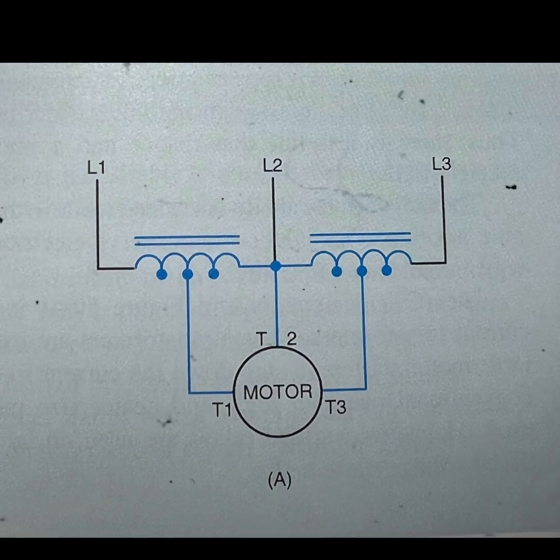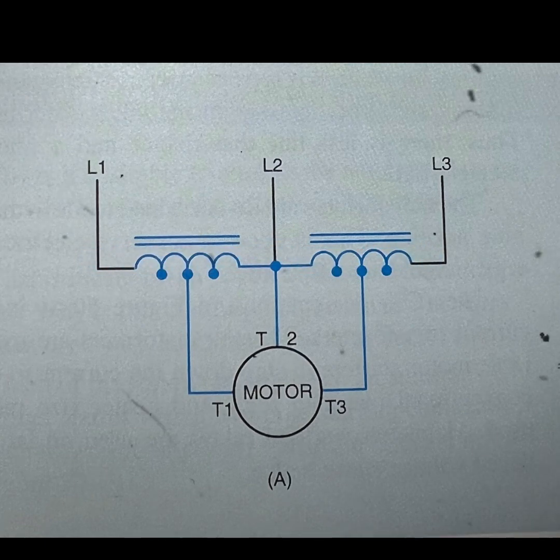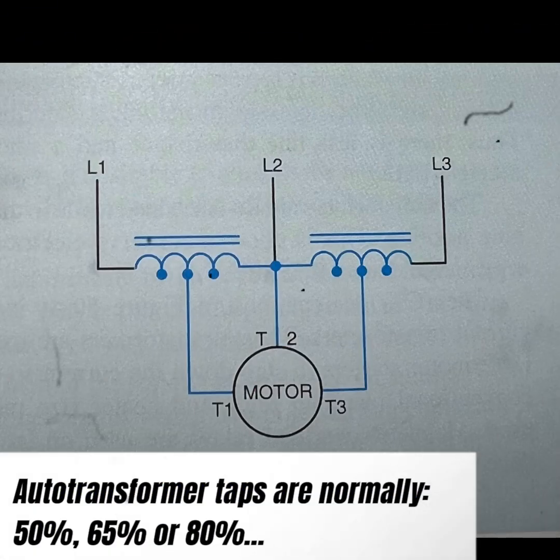Auto transformer reduced voltage starters are similar to primary resistor starters in that they are used primarily with an AC squirrel cage motor to limit the inrush current or to lessen starting strain on driven machinery. This type of starter uses auto transformers between the motor and the supply lines to reduce the motor starting voltage. Taps are provided on the auto transformer to allow the user to start the motor at approximately 50%, 65%, or 80% of line voltage.